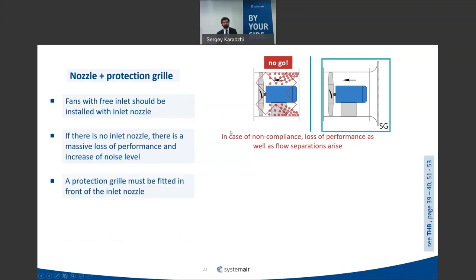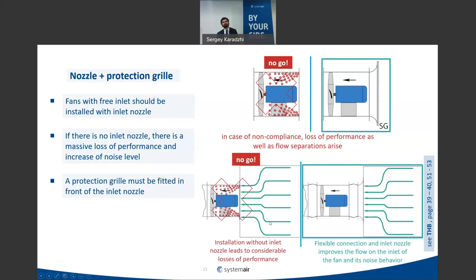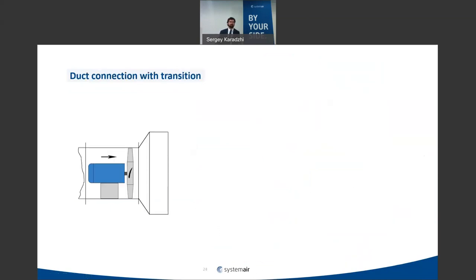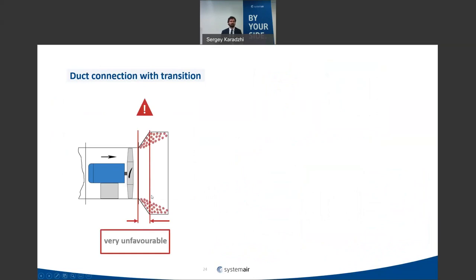If you have a chamber in front of the fan without an inlet nozzle, separation of flow will again reduce fan parameters. Flexible connections should always be installed to separate vibration distribution into the duct system. Regarding transition pieces: if you have a duct much larger than the fan diameter with a transitional piece, don't make it too short — otherwise you will have flow separation and high losses.